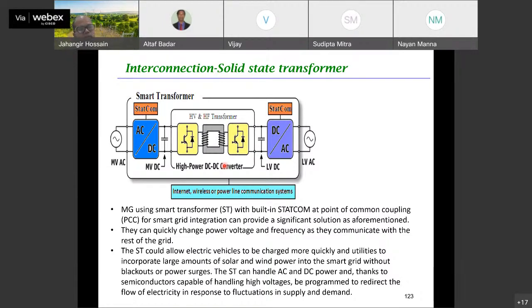But this is one of the future devices, and it's a very smart device - you might have heard about the solid state transformer. Many universities are doing research on this. It's still not a commercially viable option in the market now, but hopefully it might come in the coming years. It's not only a normal transformer where you have step up or step down based on primary-secondary number of turns, but on top of that you have AC to DC inverter/converter on both sides, which can provide the STATCOM function I mentioned - voltage, reactive power, power quality control. So it will not only step up or step down; this device could also be used for interconnecting your microgrid to the main grid.